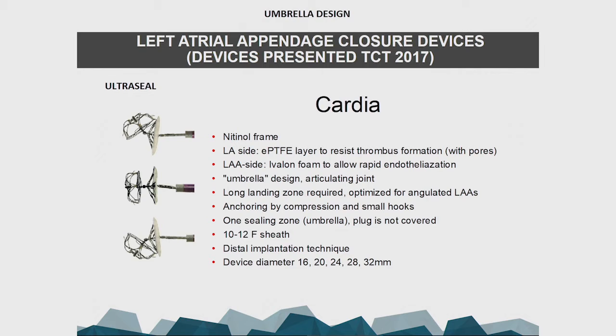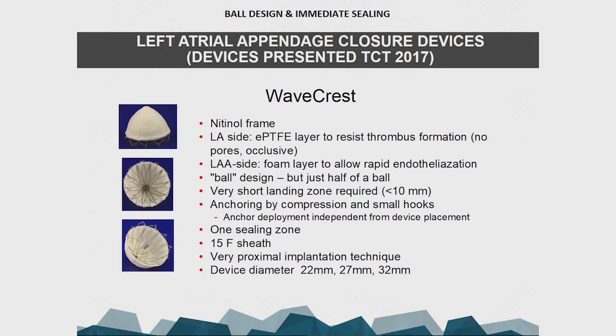Then you have the Cardia, which is also an umbrella design. There's a greater separation between the lobe and the disc. You can see there's a lot of space between the metallic parts of the device, so a lot of room for leaks. And to try to compensate this, they have a much thicker tissue covering the disc that is outside.